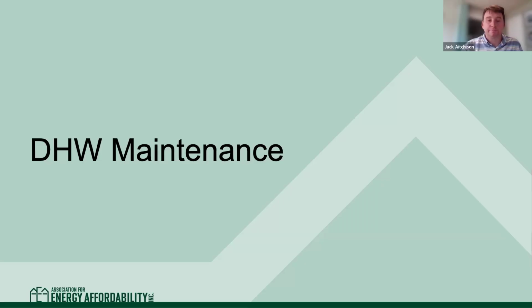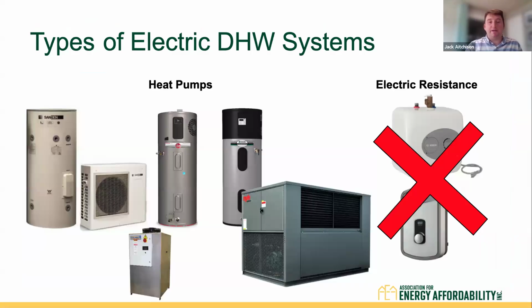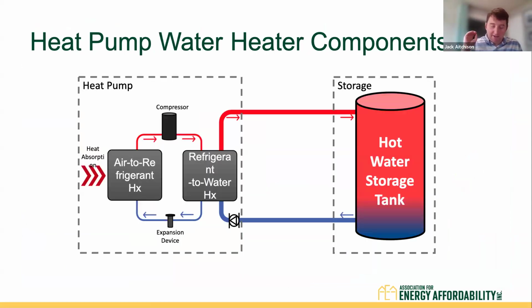Next slide. All right, now moving on to domestic hot water maintenance, types of electric DHW systems. Again, we're just going to be talking about heat pumps. Next slide. This is in between the two diagrams that I've shared, but this is again just a refrigeration cycle on the left. We have our evaporator. Remember that what's absorbing the heat is your air to refrigerant heat exchanger. That refrigerant is going from a liquid vapor mixture to a vapor, and it is absorbing heat as it goes through that phase change.